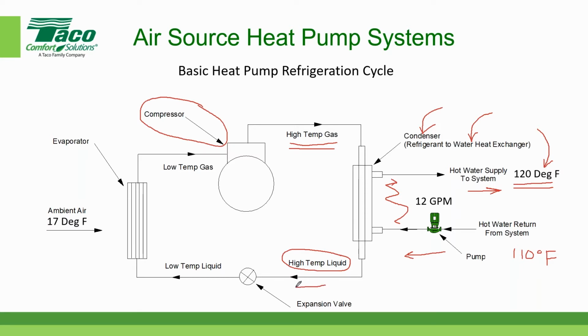And then the refrigerant continues along its cycle, passes through the expansion valve, and this is when it enters the evaporator as a low temperature, low pressure liquid. It's actually a liquid vapor mixture. And in order for it to extract heat, we could extract heat from ambient air. Ambient air, let's assume, is around 17 degrees Fahrenheit. We can actually extract heat from that air.